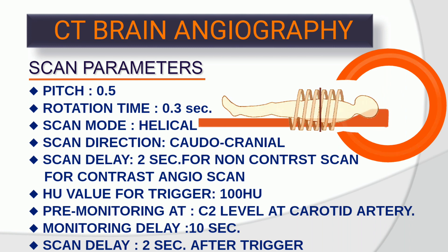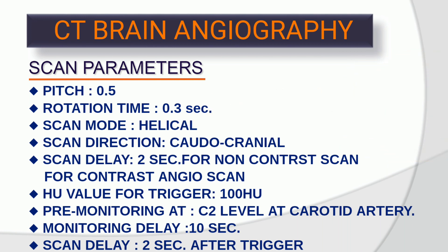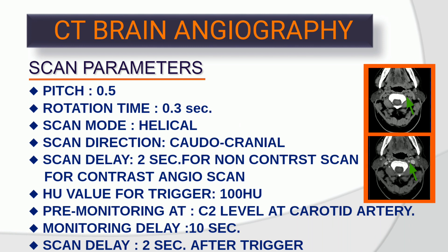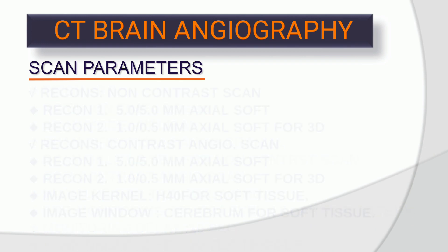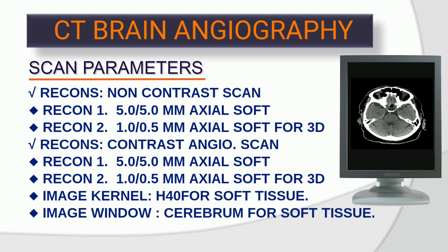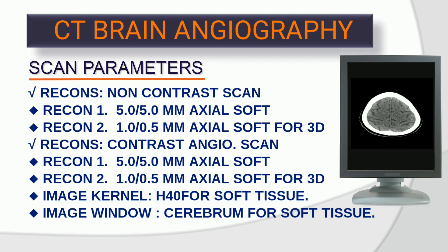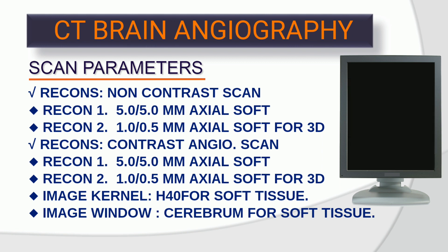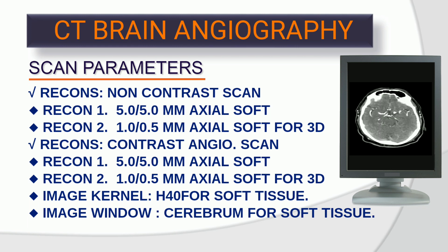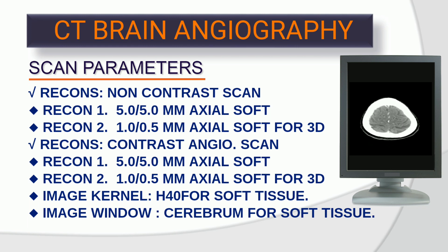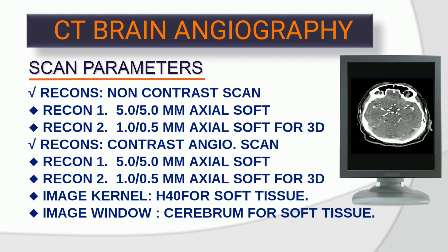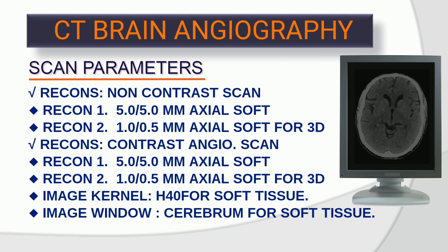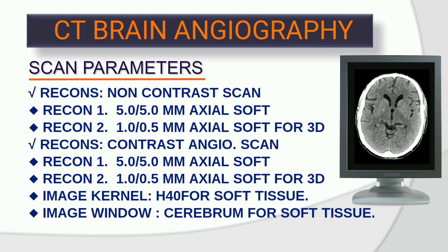Scan delay: 2 seconds for non-contrast scan. For contrast angio scan: HU value for trigger — 100 HU. Pre-monitoring at C2 level at carotid artery. Monitoring delay: 10 seconds. Scan delay: 2 seconds after trigger. Recons — non-contrast scan: Recon 1: 5 x 5 mm axial soft; Recon 2: 1 x 0.5 mm axial soft for 3D. Contrast angio scan: Recon 1: 5 x 5 mm axial soft; Recon 2: 1 x 0.5 mm axial soft for 3D. Image kernel H40 for soft tissue. Image window: cerebrum for soft tissue.